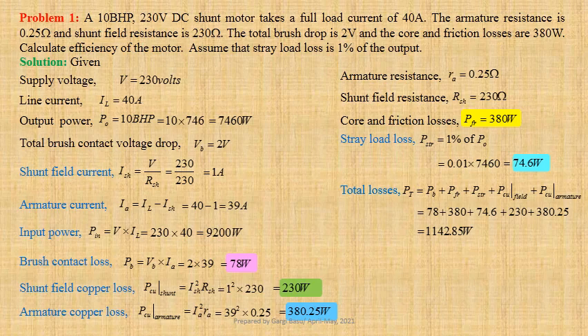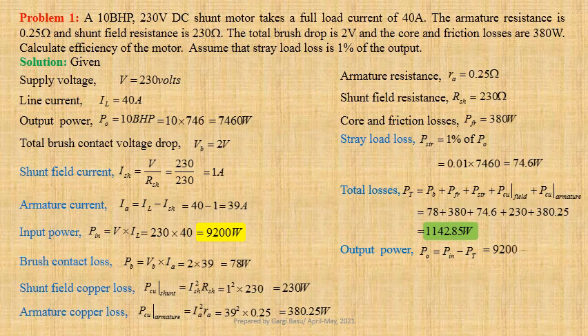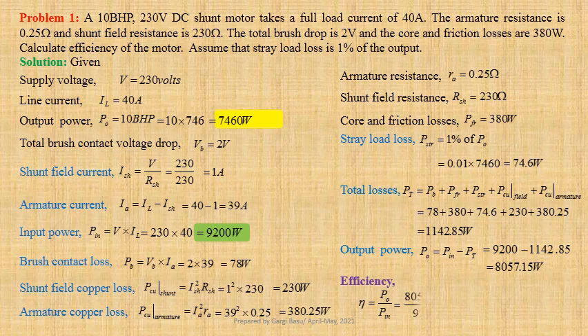By subtracting total losses from input power we get output power. PO equals PIN minus PT, that is 9200 minus 1142.85, giving us 8057.15W. Efficiency: eta equals PO by PIN, that is 8057.15 divided by 9200, giving us 0.8758 per unit or 87.58%.